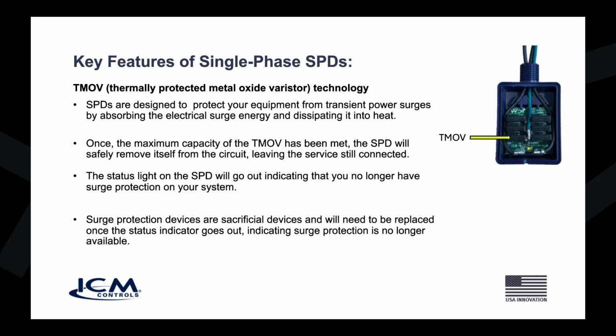But what that does is it leaves you connected so you don't have an instant loss of power. What you will have is the status light on the SPD will go out, and that indicates you no longer have surge protection. It would need to be replaced immediately. Surge protective devices like the ICM 517A and the 517A Lite are sacrificial devices. In other words, they need to be replaced once the status indicator goes out and protection is no longer available.